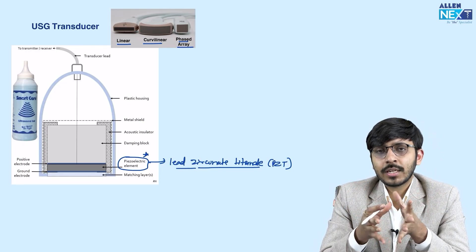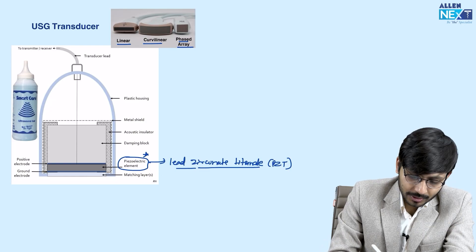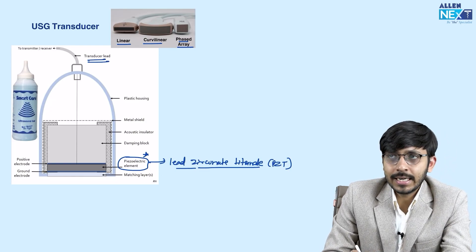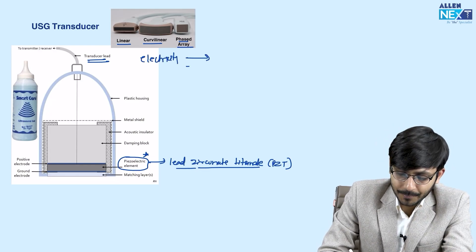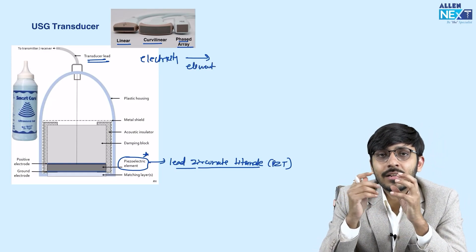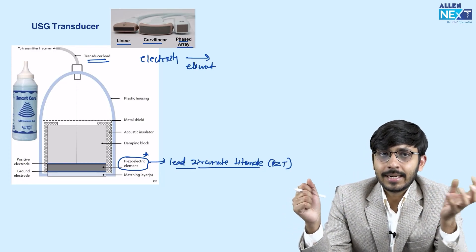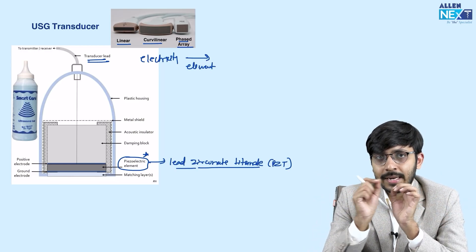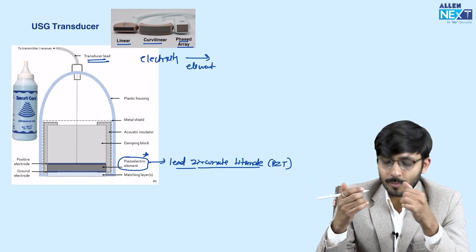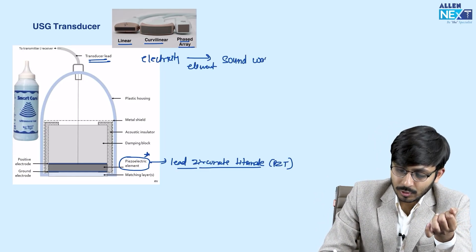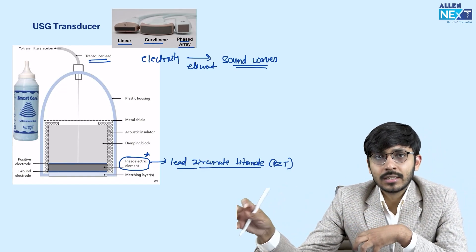All these ultrasound probes share some basic principles. How is a sound wave produced? The ultrasound transducer is connected to the electric supply, and when electricity is passed through the piezoelectric element, compressions and rarefactions are induced into the crystal. The crystal undergoes vibrations secondary to electrical stimulation, and these result in formation of sound waves. The piezoelectric element converts electrical energy into mechanical energy in the form of sound waves.